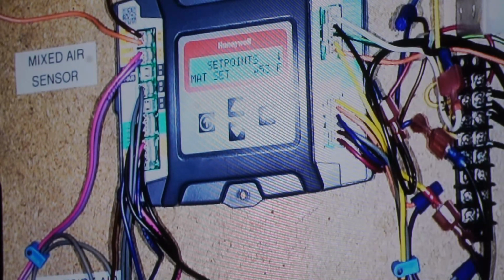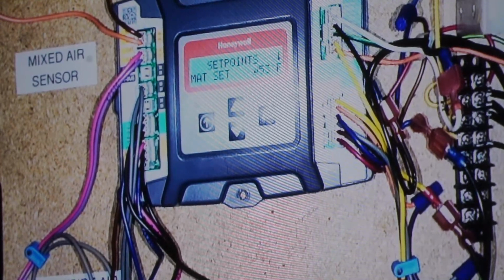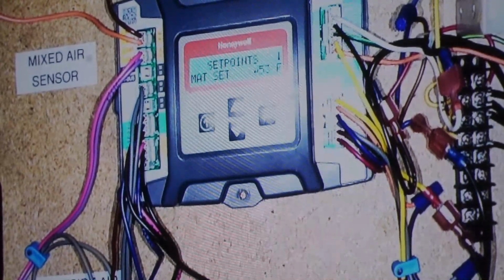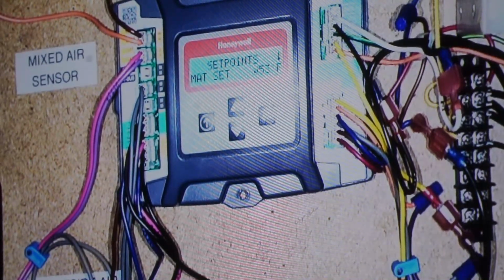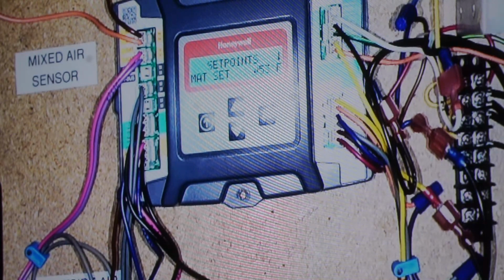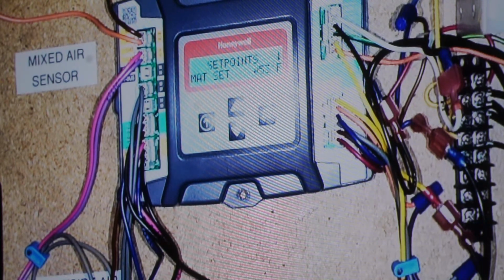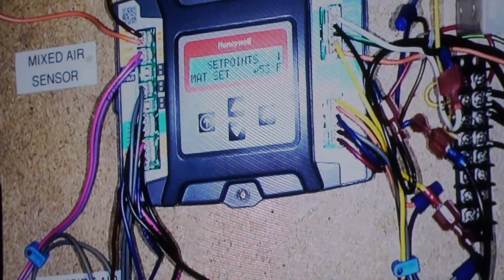But back in the day you heard the term wild economizer, so there would be a sensor on the outside air that, hey, it's 50 degrees outside, I got a call for cooling, 100% outside air. That's wild. We have no control of the mixed air temperature sensor, and we're dropping whatever temperature is out there. It ain't gonna work, because that 55 degree air with the entrained air is going to come out in the space, and it's going to be comfortable when we need cooling. 40 degree air is going to drop like a lead balloon. It's just going to fall, and it's going to fall right on my bald spot. It's going to irritate me, or females or anybody else. So we never want that to get much below 50 degrees, 53 degrees, unless it's processed. So you got a big piece of machinery there, I want as cold air as I can get on it. That's where we can change that.